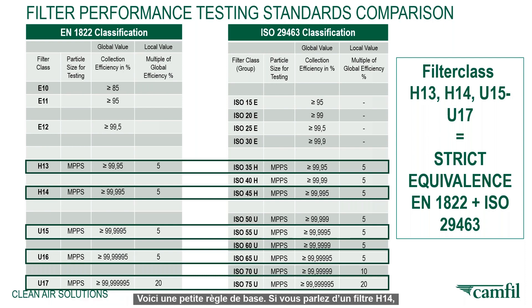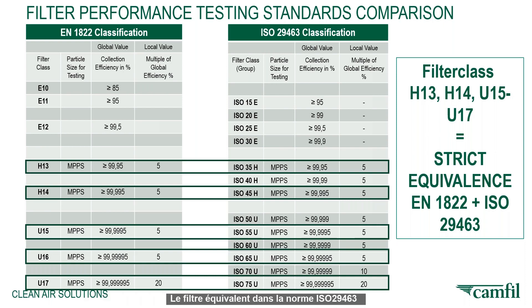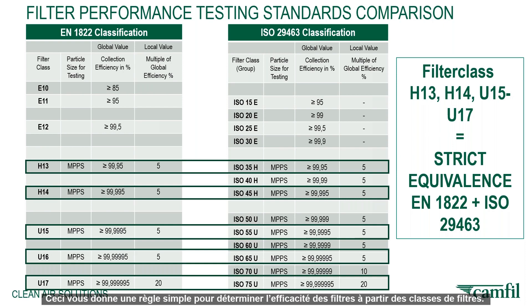A little rule of thumb: if you're talking about a H14 filter, H14 means four nines. So your efficiency at MPPS will be 99.995% — four nines. The equivalent filter in ISO 29463 would be ISO 45H, where 45 represents four nines and a five — so 99.995%. This gives you a quick way to figure out efficiency from the filter class.